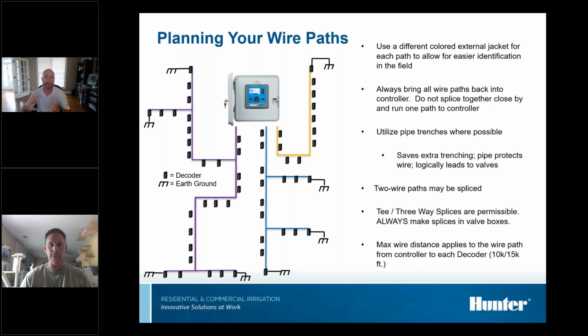So when you're designing this out, when you do multiple 2-wire paths, you want to use a different colored external jacket. We'll talk about the wire in a minute. It's available with different colors of the outer jacket. And the reason for that is so if somebody's digging out in the field 500 feet from the controller and they get down to the 2-wire path and there's 3 2-wire paths running, if they're color coded, they're going to know which one is which in the field without having to break it open or anything like that.